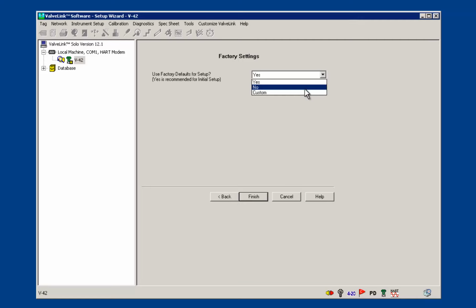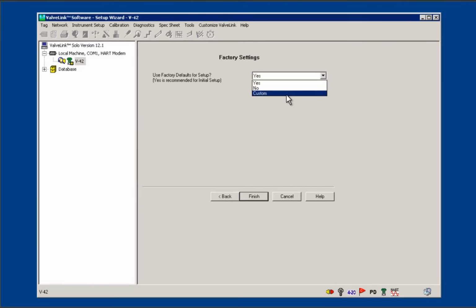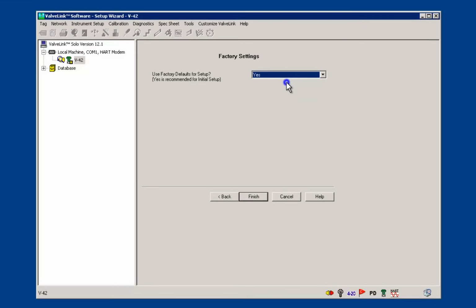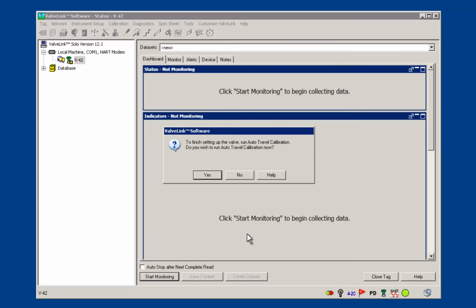If this is the first time you are running the setup wizard, you can choose Yes for factory defaults, but if your instrument may have previous settings, you'll lose some by choosing Yes. Selecting No will preserve any previous values. Choosing Custom allows you to change options independently, but we are assuming an initial setup this time. Click Finish and the Setup Wizard will apply your user settings. The DVC6200 digital valve controller is now configured and the next step is to calibrate it.